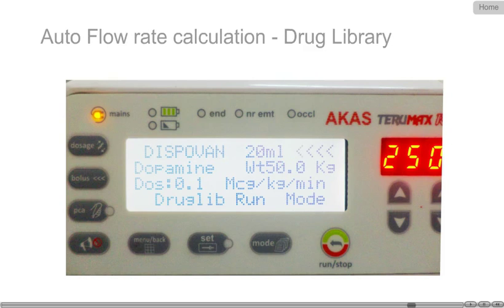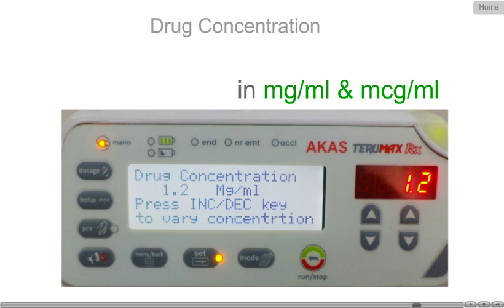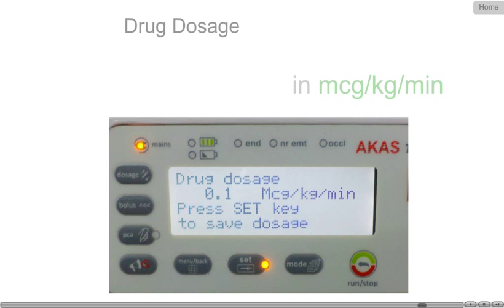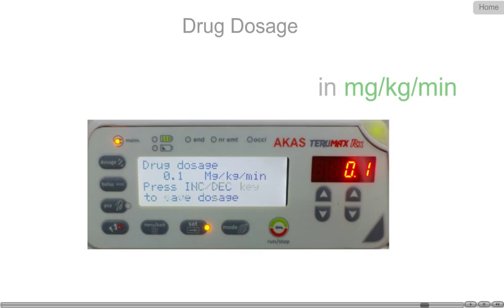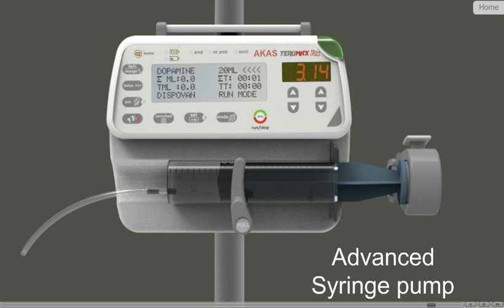Drug dosage is automatically calculated and infused when the patient's weight, drug concentration, and drug dose in MCG per kilogram per hour or per minute is keyed in. To summarize, AKAS TeruMax Rx is a unique combination of interface and drug dosage options.